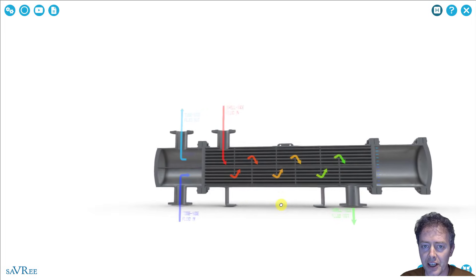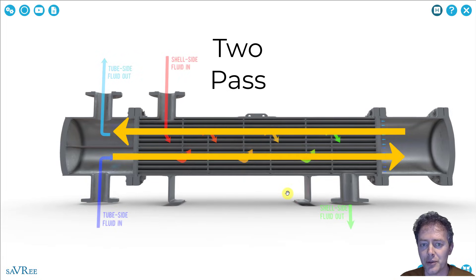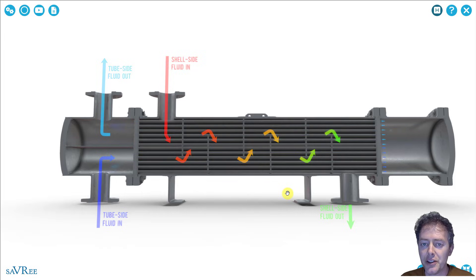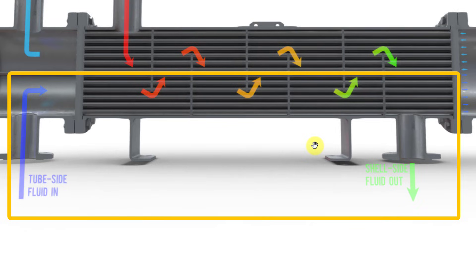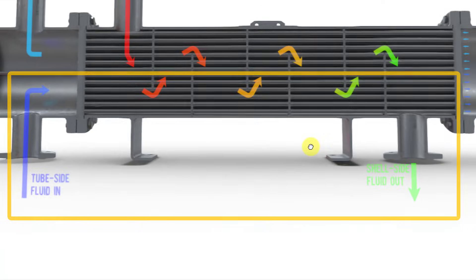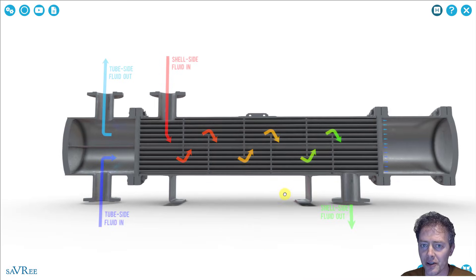This type of heat exchanger is called a two-pass heat exchanger, once again named after how many times the tube side fluid passes through. In our example, the tube side fluid flows left to right and then right to left — that's what makes it a two-pass heat exchanger. In the lower half, the tube side fluid flows in parallel with our shell side fluid, but in the upper half it flows counter to the shell side fluid. We also have some cross flow as the shell side fluid crosses over the tubes several times.